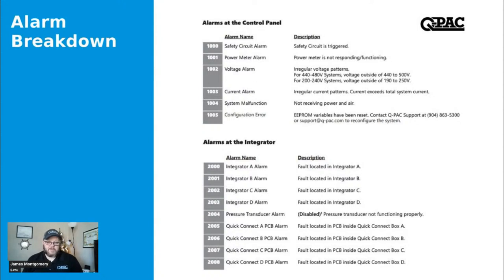But good question. So nothing outside of 1000 is a shutdown. The world's not on fire. You're getting good use of your system. If it's just running in hand mode, and you don't even have the rest of your BAS system set up, it's not a huge issue. Yeah, you've got an alarm and it's going to be annoying. It's going to go off every few minutes. You're going to have to acknowledge it or hear it go off until you do, but it's not a shutdown.